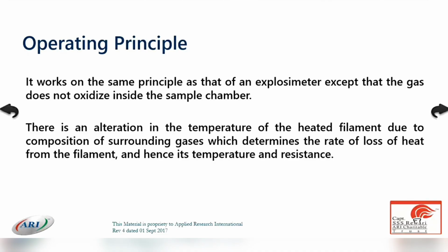So it works on the same principle as the explosimeter, except that the gas does not oxidize inside the sample chamber. There is no oxidation taking place because the tank scope is used in an inerted state, whereas the explosimeter is used in a gas-free state. When it is in the inerted state, the oxygen percentage is less than 11%, so oxidation will not take place.